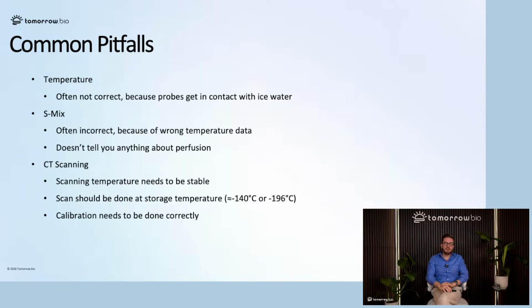The problem in general is that even if you use the nose or tympanic, it doesn't matter, since you have ice water flowing around the patient, potentially above the ears, and in our case always above the ear line, to be able to cool faster, these temperature probes can get in contact with ice water. So if you have very, very fast cooling rates, very low ischemia times if expressed in S-Mix, those are not realistic. With current technology, if someone says they've been cooling the patient between 0.5 and 1 degree per minute, that's not possible with current technology. That means the temperature probe was somehow exposed to ice water. So it needs to be a realistic temperature curve, right?